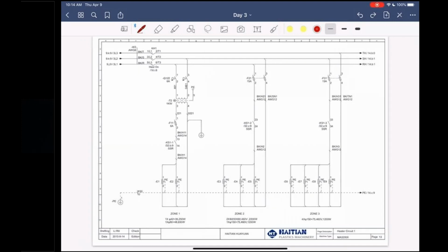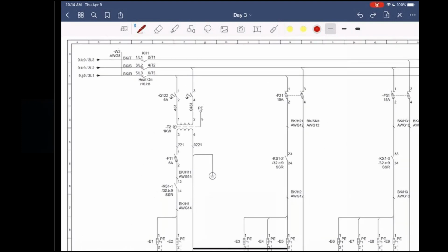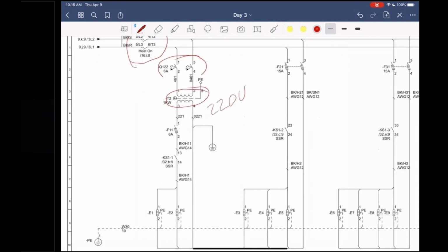Heater circuit. Again, you have American wire gauge number 8 going into this RST, your heat-on circuit breaker, contactor right here, KH1. So when you push the heater on button, KH1 energizes, closing those contacts. The power then goes through Q122, which is a 6 amp, and that's going through T2 transformer. Again, the T2 transformer is taking the 480 volts and transforming it into 220 volts for the front zone nozzle heater bands.